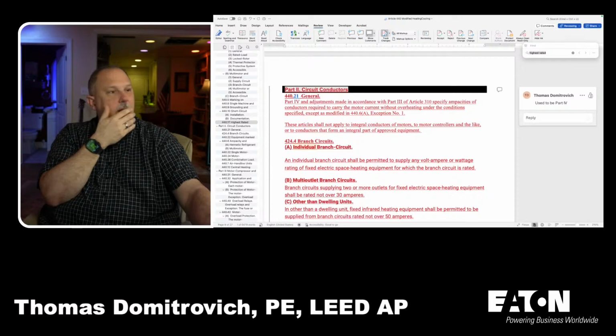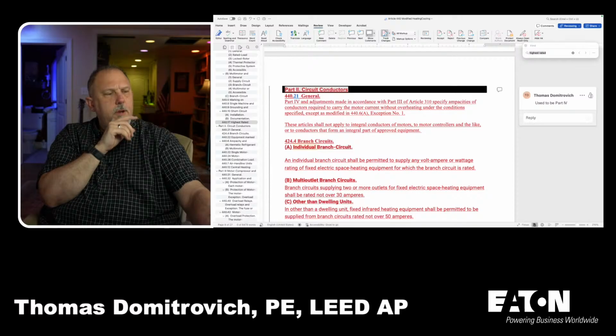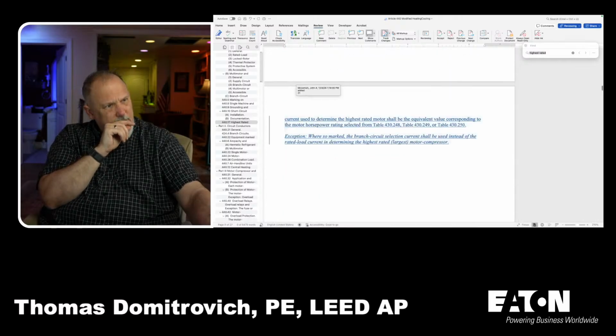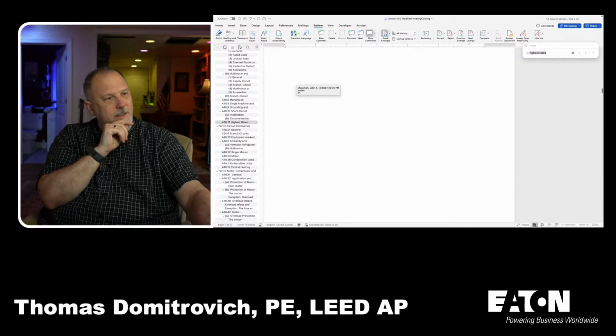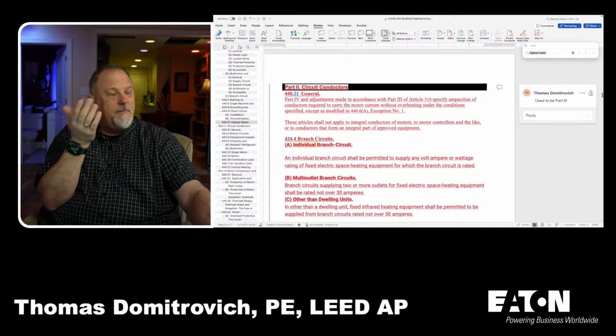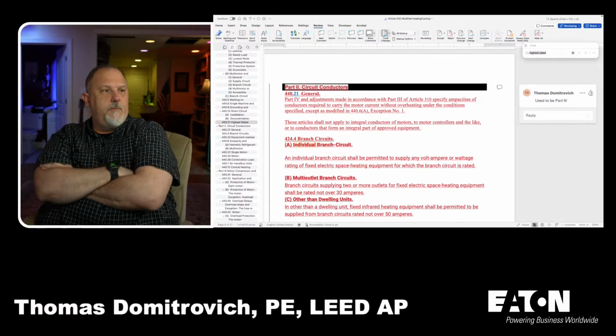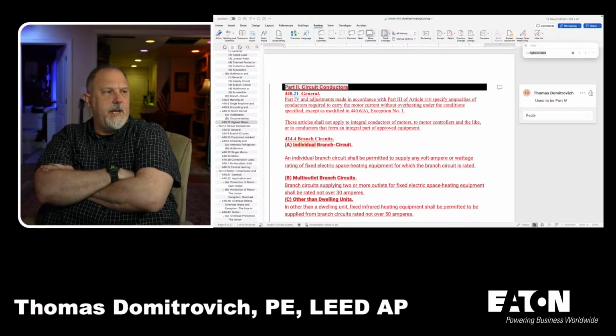Makes sense. All right, so part 4, 440.21. Let's make sure it's 440. Yeah, 440. Jeez, I'm in 440, Tom. 440.21, general. Part 4, and adjustments made in accordance with Part 3 of Article 310, specify ampacity of conductors required to carry the motor current without overheating under the conditions specified, except as modified by 440.6(A), exception number 1.